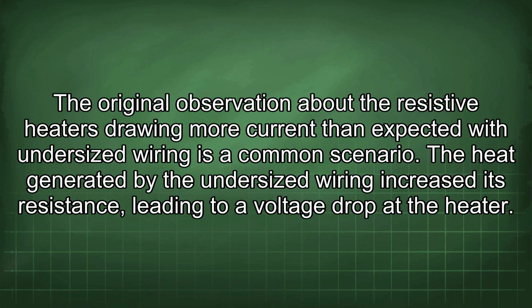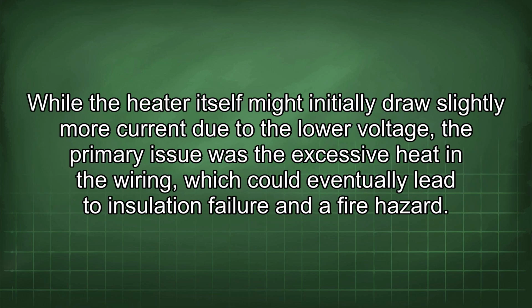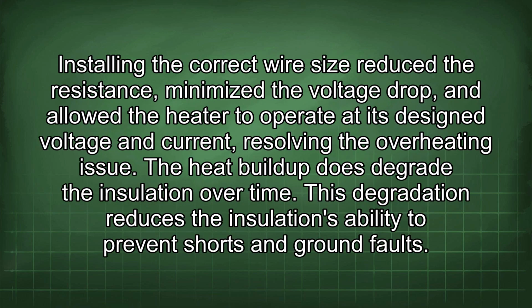The original observation about the resistive heaters drawing more current than expected with undersized wiring is a common scenario. The heat generated by the undersized wiring increased its resistance, leading to a voltage drop at the heater. While the heater itself might initially draw slightly more current due to the lower voltage, the primary issue was the excessive heat in the wiring, which could eventually lead to insulation failure and a fire hazard. Installing the correct wire size reduced the resistance, minimized the voltage drop, and allowed the heater to operate at its designed voltage and current, resolving the overheating issue.